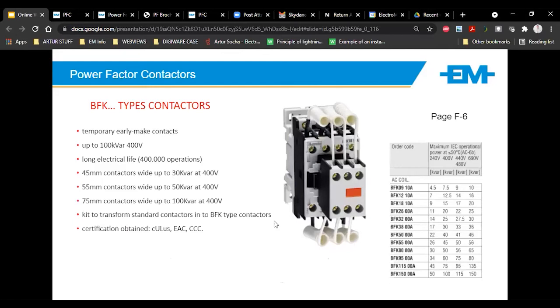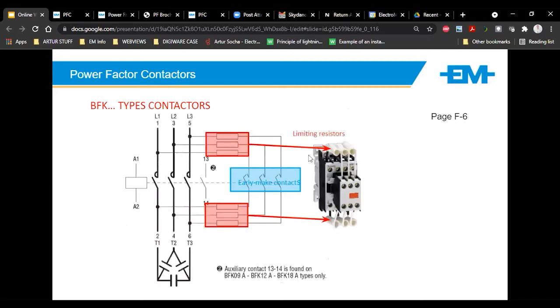Within the PFC systems, obviously we do the contactor. On a normal system, we've got these little blocks with current limiting resistors on. That is to limit the inrush current seen by the contactor. So when you step in that capacitor bank, these resistors limit the inrush current before the contactor sees it. So it's very important to use specific contactors for power factor systems. Okay. Not just, I think it's 50 amps and I just stick a 50 amp contactor in. Make sure you've got product that's got current limiting resistors, especially if you do non-reactive based systems.